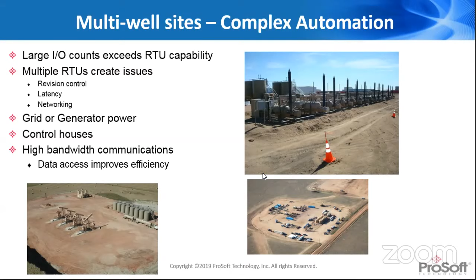So with the amount of automation on those sites, what we're seeing is a lot of installations where you're using one or multiple standalone flow computers to do the measurement, and then often using something like a Rockwell controller, CompactLogix PLC, to do the automation on those sites. Sometimes you're using gateways or RTUs to network back and forth between the two devices. As we're doing the commissioning and setup of these sites, it increased the overall amount of time it took to actually commission and set these up.